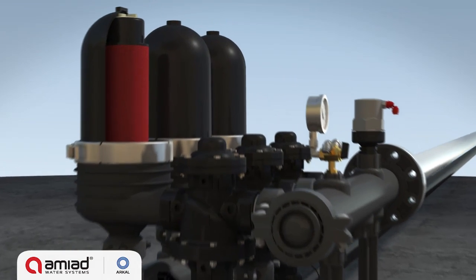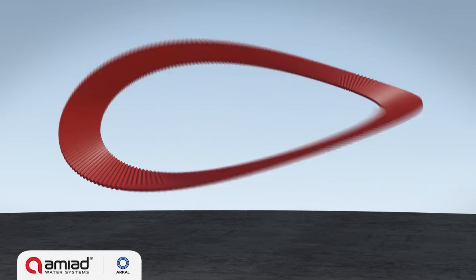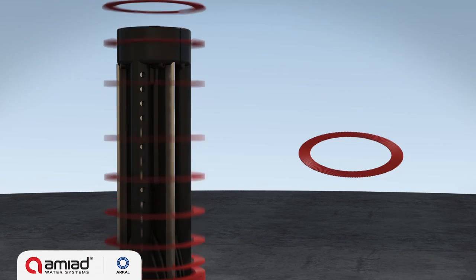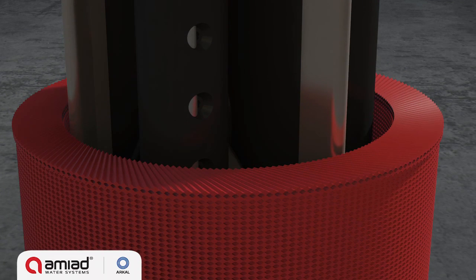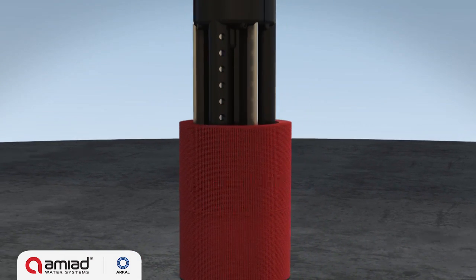Each filter module consists of a filter housing with a central spine on which the SpinKlin discs are stacked. These thin color-coded groove discs are diagonally grooved on both sides in opposite directions. A series of discs are stacked and compressed on a specially designed spine, creating a matrix of consecutive crossing points which form multiple particle traps.